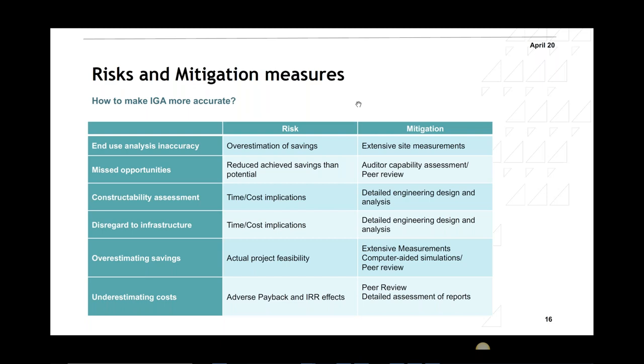Constructability assessment. Sometimes the auditor or the ESCO comes up with an idea that is not buildable. So we need to have proper detailed engineering analysis. That would be the mitigation. Disregard of infrastructure as well. Sometimes the ESCO or the energy auditor would propose something that disregards the infrastructure. It's not going to work without the proper infrastructure that's not there in the building. We faced that one time when they were adding VFDs on some panels and there was not proper grounding because the building was very old, and whenever they turned the VFDs on, it would trip.